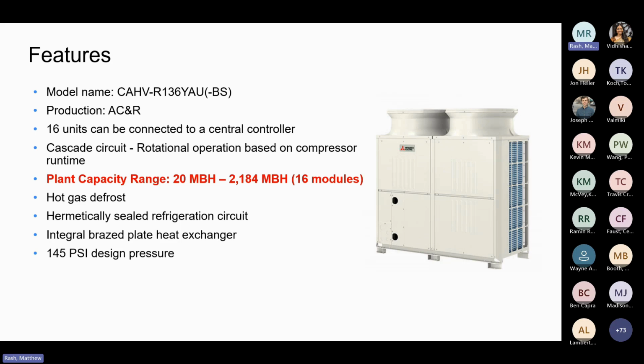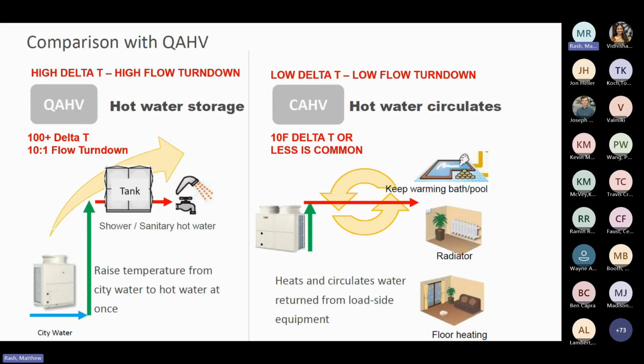Again, the other product that we're launching soon that I mentioned, CAHV, that'll be at the AHR show as well as the QAHV product. This is built for low delta T, much more simple in terms of application, again, geared for typical closed loop heating hot water applications. It's not potable rated either, but it could be used for domestic hot water. I'll try to show an example of that if we have time. But it has to be applied differently.